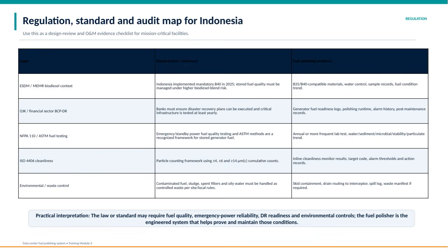Additionally, we have fire and safety standards like NFPA 110 and ASTM fuel testing methods, which provide frameworks for testing emergency power fuel quality. Labs should test fuel at least annually, checking for water, sediment, microbial contamination, stability, and particulate levels to maintain high fuel quality.